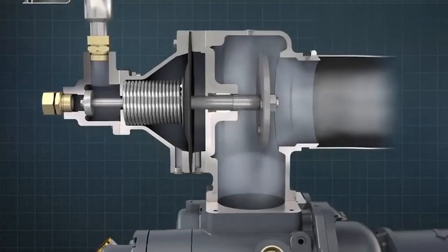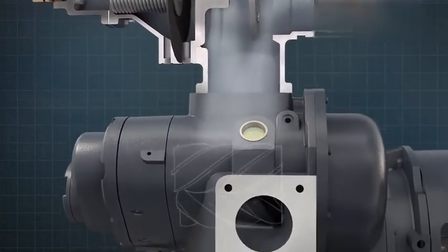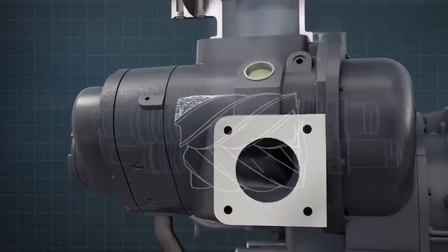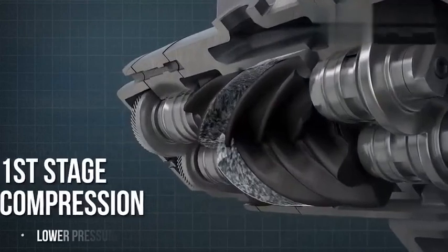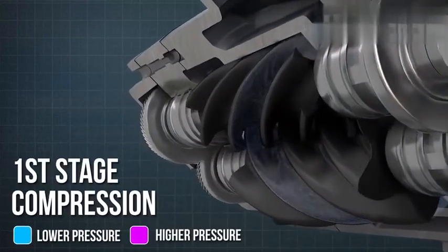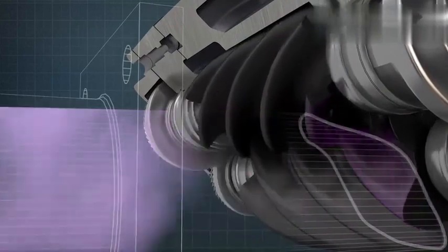The air enters the first stage via the air intake valve and is trapped between the lobes and flutes on the underside of the compression rotors. As the rotors turn, the volume of the trapped air reduces, compressing the air and driving it towards the delivery port at the back of the air end.